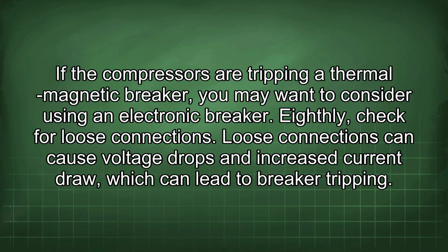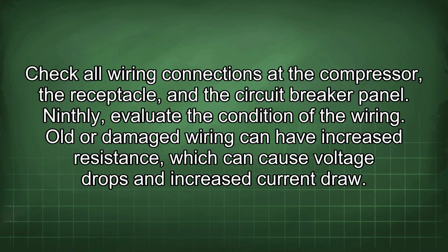Eighthly, check for loose connections. Loose connections can cause voltage drops and increased current draw, which can lead to breaker tripping. Check all wiring connections at the compressor, the receptacle, and the circuit breaker panel.